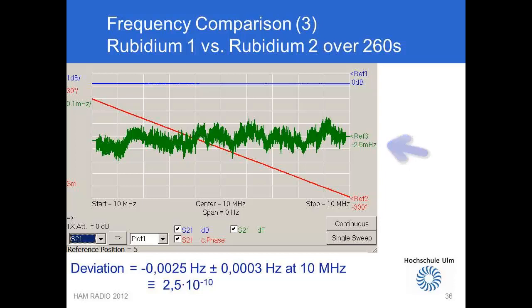It is possible to directly read the frequency difference provided the frequency span is 0. We are thus measuring at the same frequency while the time increases from left to right, and as the phase difference is not 0 but drifting, the frequency difference is calculated to minus 2.5 millihertz, and the phase variation is about 300 degrees, as even a Rubidium oscillator is not fully stable.